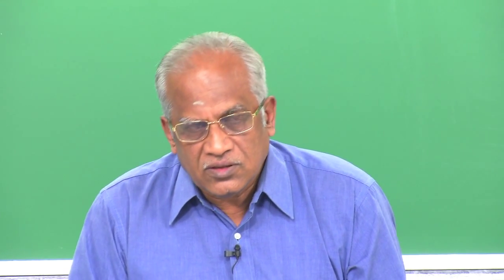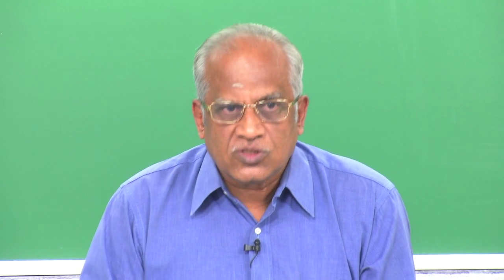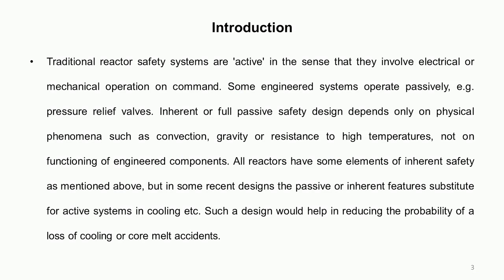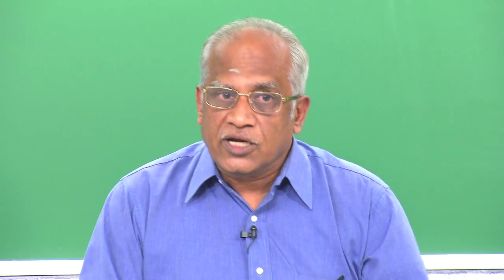It is difficult to make everything passive, so in all reactors there is an element of active safety features and an element of passive safety features. The idea is that by introduction of passive safety features, we are not depending upon active components that can fail on demand, and thereby we are reducing the probability of core cooling not happening or a reactor shutdown not happening — reducing the probability of failure of a shutdown or decay heat removal, thereby contributing to safety.